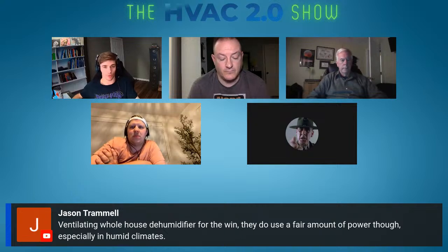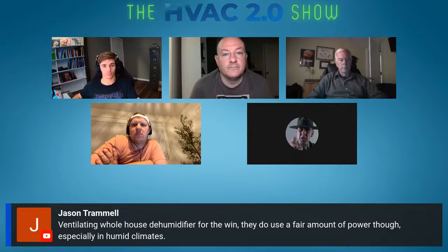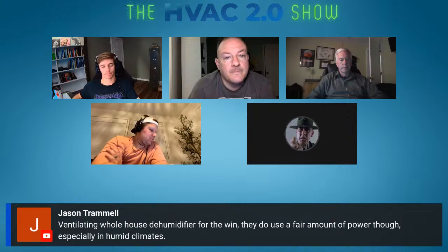And having electric reheat is just kind of that special sauce to really eliminate the need for dehumidifiers in general. Outside of retrofit systems already in place that have a humidity problem and you need to get it in control, then that's where dehumidifiers are great all day long. And if you're using a lot of energy dehumidifying, you probably want to do a blower door test, because you might be trying to dehumidify the outdoors.